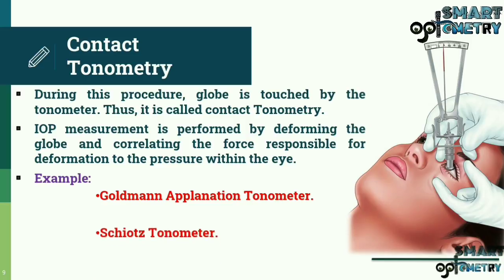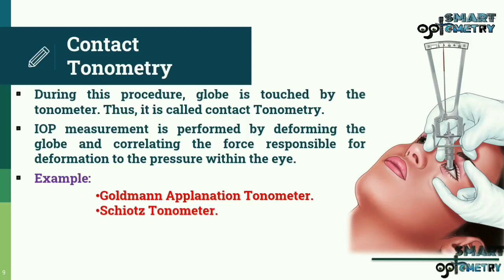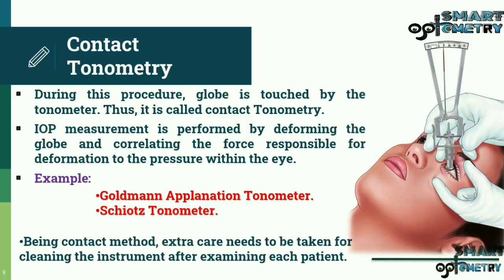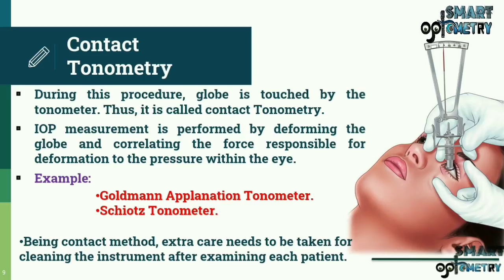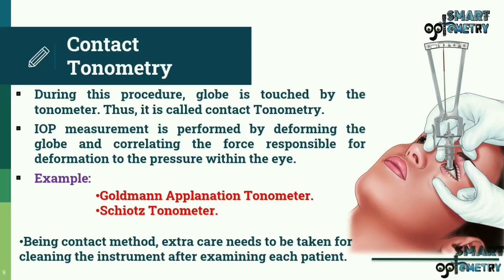Examples of contact tonometers include the Goldmann Applanation Tonometer and the Schiotz Tonometer. Being a contact method, extra care needs to be taken for cleaning the instrument after examining each patient.